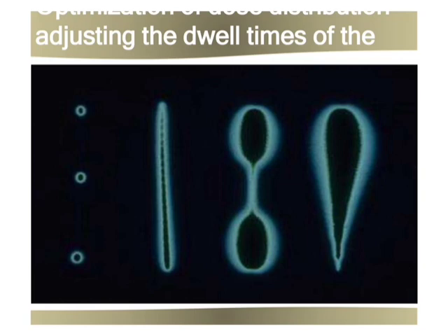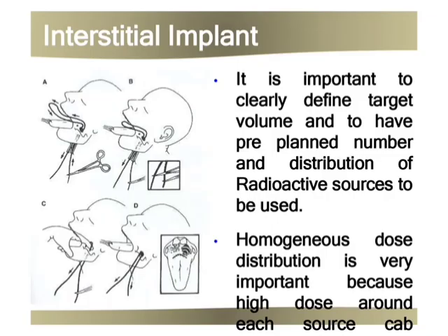So the source movement is the combination of various source trains, with the option to choose a small miniature source with a spacer, enabling the operator to create their own source configuration. Because by increasing the dwell time, we can design the shape of the radiation area. So according to that, we can plan the tumor by this source.